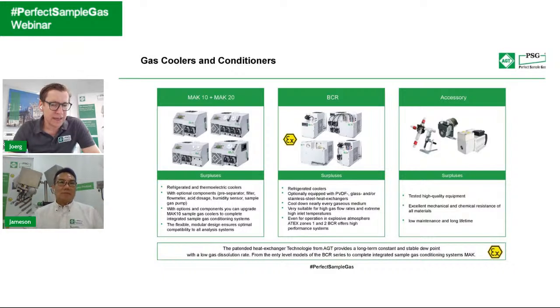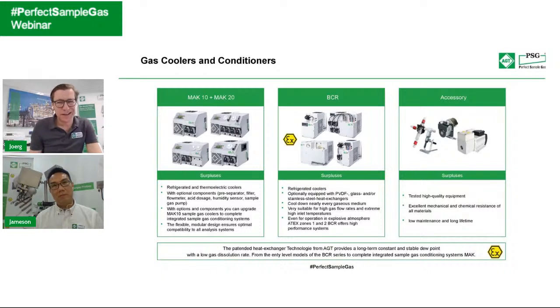But like Jameson says, if you choose the wrong heat exchanger, the wrong layout, that could also be crucial. If this happens, what can you do? Maybe an additional cooler, which could cause additional problems, because then you have the second stage cooling in a different place. So in this case, we would also recommend including it in your calculation. This is not a really quick fix, because you already made the wrong selection, but it's important to give yourself a little buffer, a capacity buffer, so that if something changes, you will be on the safe side.